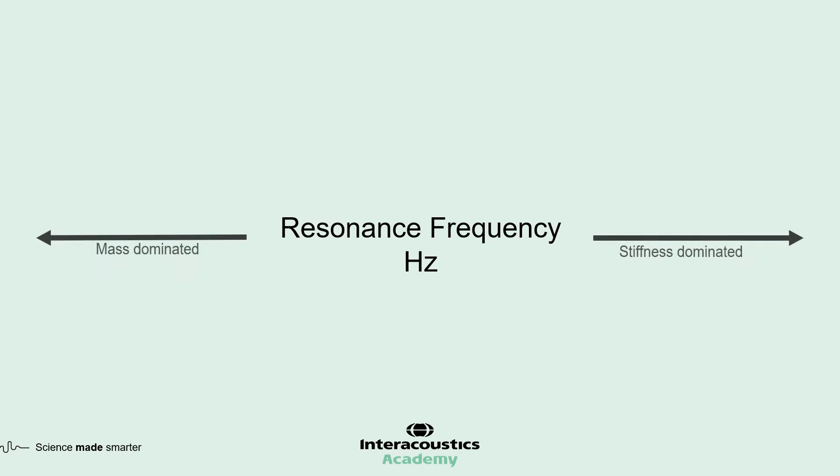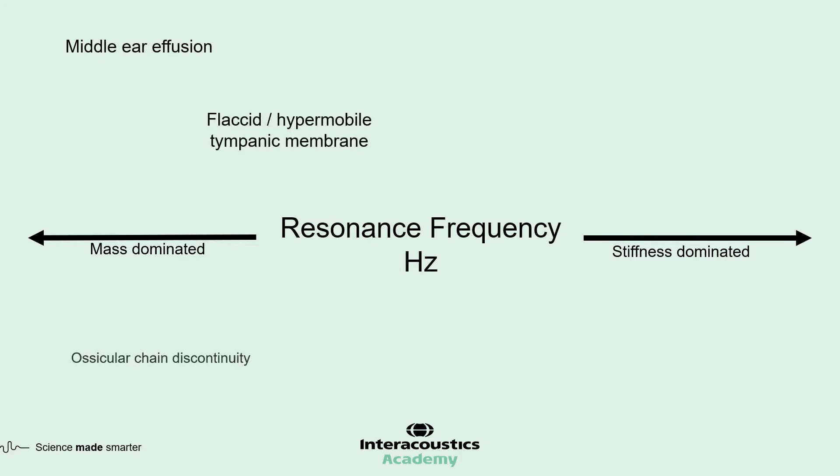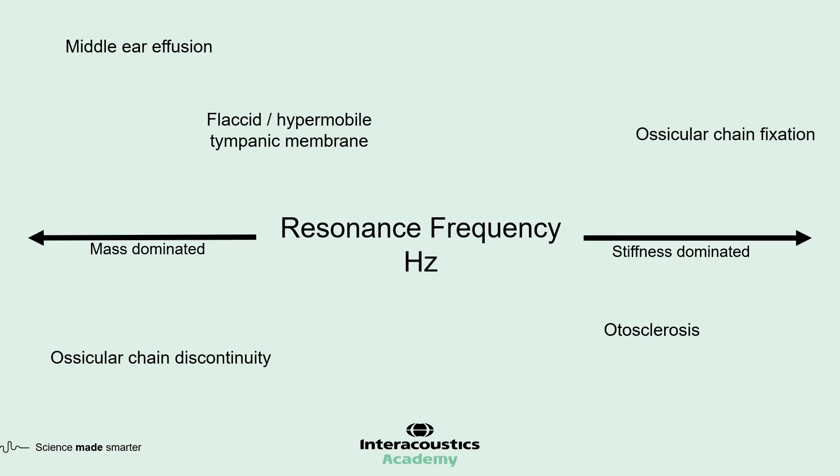A mass dominated pathology such as middle ear effusion will show a decrease in resonance value or no recording at all. Similarly, ossicular discontinuity pathologies will show a decrease in resonance frequency. A stiffness dominated pathology such as otosclerosis will show the resonance frequency shift to a higher frequency. Ossicular chain fixation is likely to show an increase in resonance frequency due to the increased stiffness, whereas a flaccid tympanic membrane would typically show a decrease in resonance frequency because of the greater elasticity.